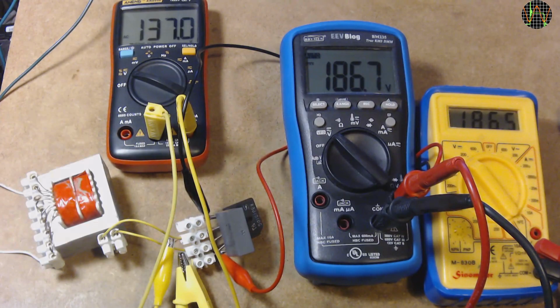In this demo, the effect is relatively mild, but depending on the time of day, the fluctuations can be much more severe, such that it's hopeless to compare two instruments. While reading the voltage on one, the value is changing already, so the second meter reading can't be compared with the first one. Clearly, I would need a stabilized AC as input for this setup, but sufficiently stabilized AC power supplies are rare, and those that exist are big, bench or rack mounted monsters and prohibitively expensive.